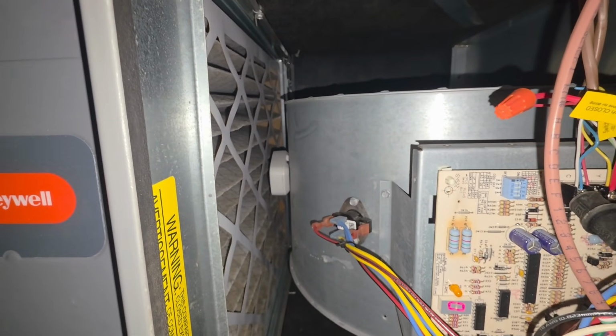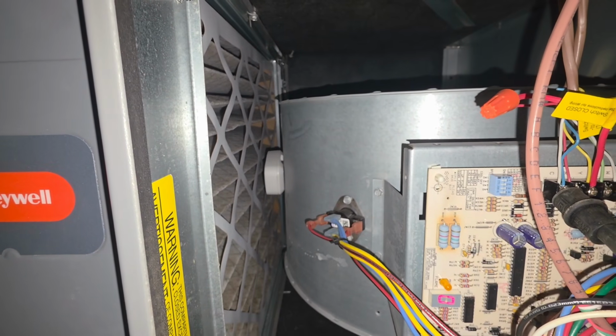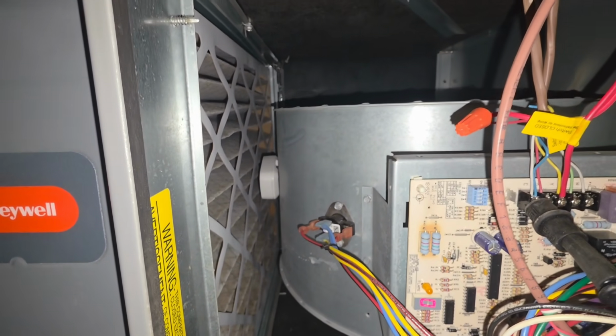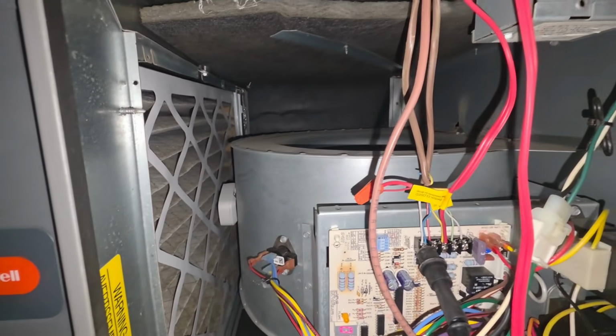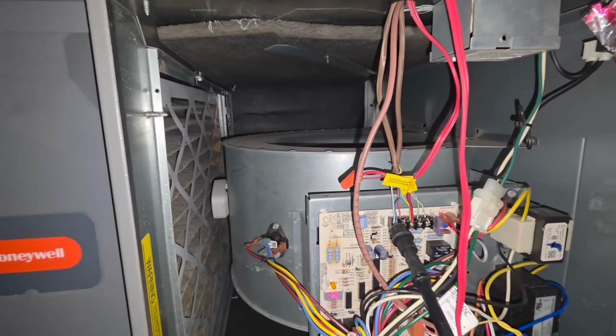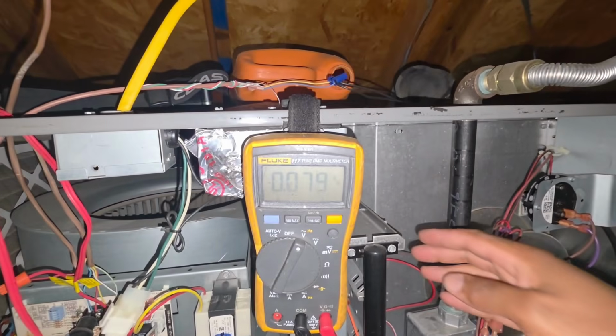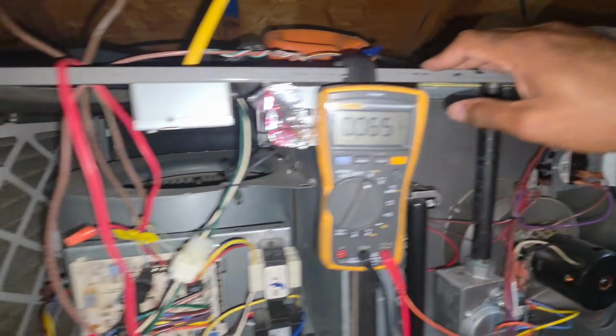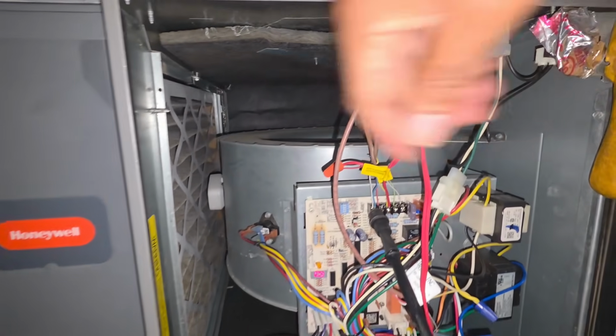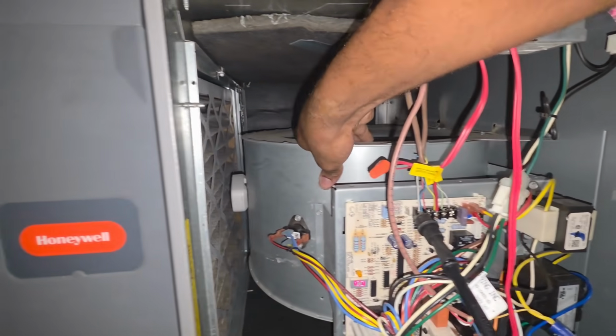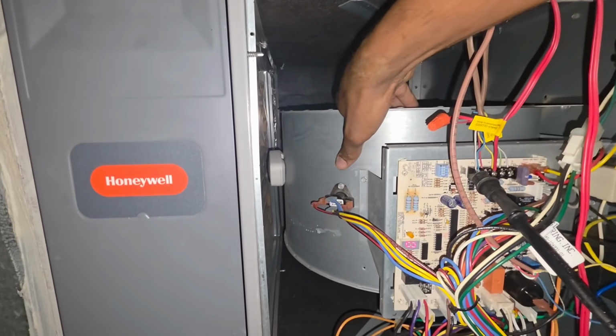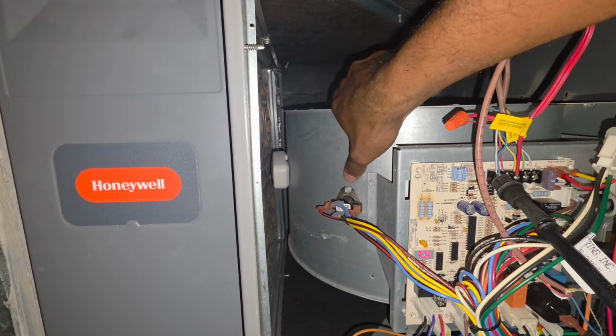A lot of times we forget about just the limit switch for the blower motor. If that blower is not working, it's going to get real hot up in there because your heat exchanger is kind of connected to the furnace, and this whole cage will get hot, and that limit switch will sense that.